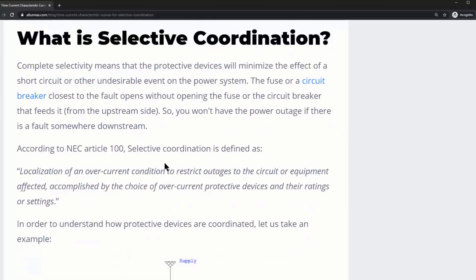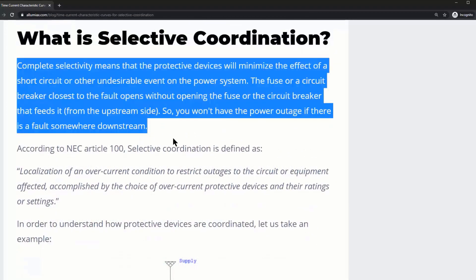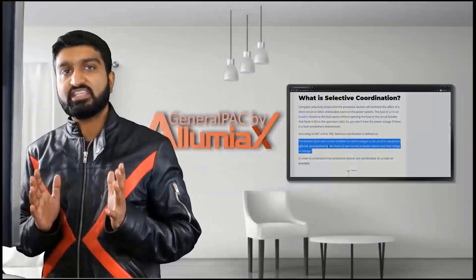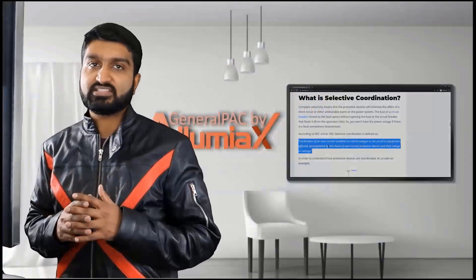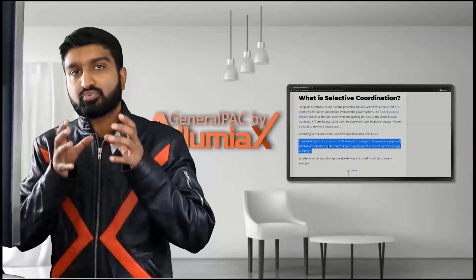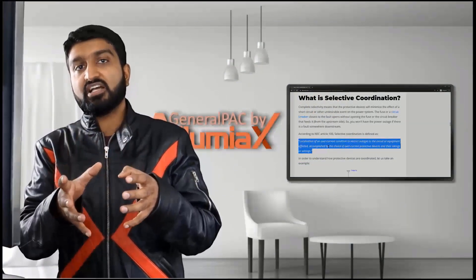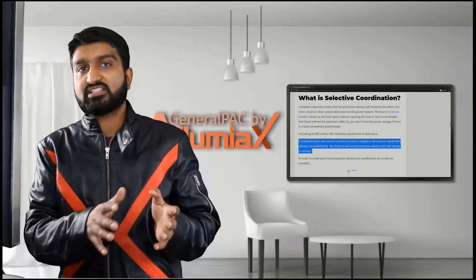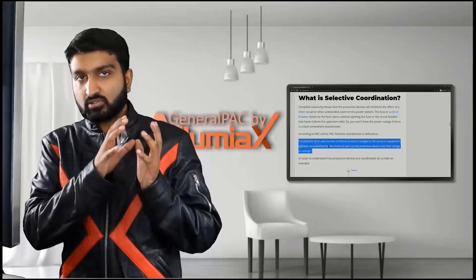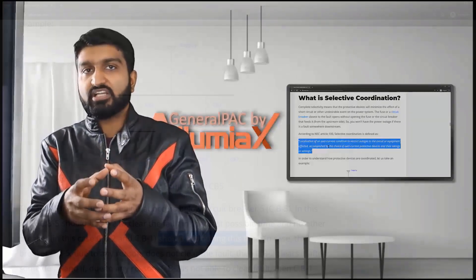What is selective coordination? Complete selectivity means that the protective device will minimize the effect of a short circuit or other undesirable events on the power system. What we're saying is that the closest breaker that feeds that particular faulted area is the one that actually operates and localizes that problem area.